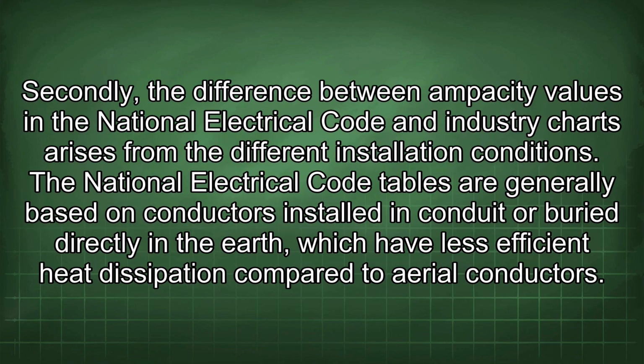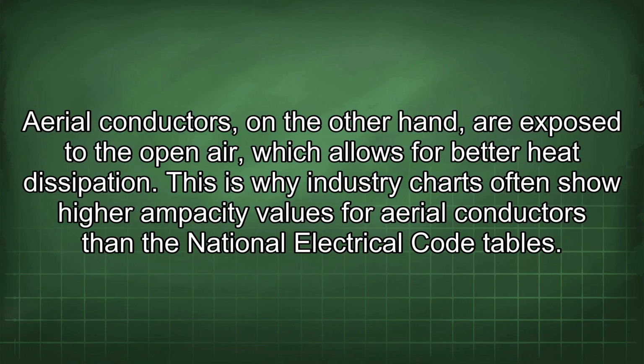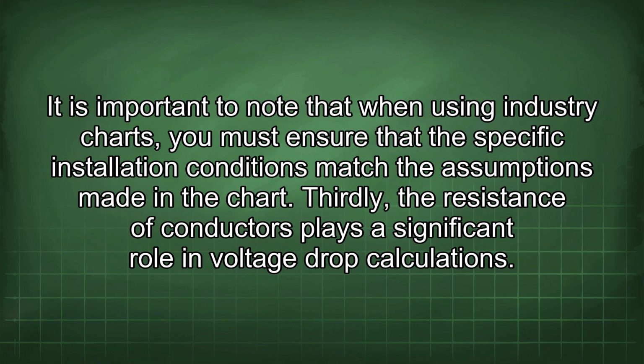Secondly, the difference between ampacity values in the National Electrical Code and industry charts arises from the different installation conditions. The National Electrical Code tables are generally based on conductors installed in conduit or buried directly in the earth, which have less efficient heat dissipation compared to aerial conductors. Aerial conductors, on the other hand, are exposed to the open air, which allows for better heat dissipation. This is why industry charts often show higher ampacity values for aerial conductors than the National Electrical Code tables. It is important to note that when using industry charts, you must ensure that the specific installation conditions match the assumptions made in the chart.